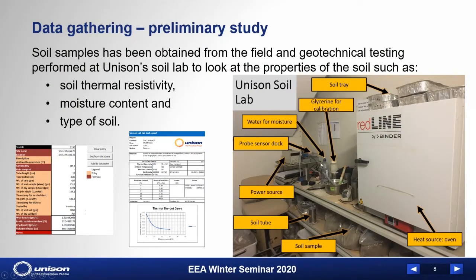Because we're in the lab, what we try to do is first dry out the soil so we have zero moisture content. Then we slowly increase the moisture by adding water. As we add water, we use the probe to measure the thermal resistivity, and we keep going until the soil cannot retain any more moisture and starts to become sludgy. That's when we stop adding moisture. We have a range we deal with anyway, so essentially from 0 to 33 tends to be the maximum.